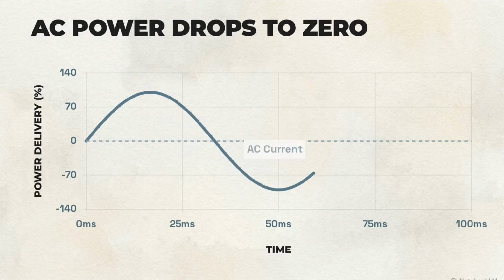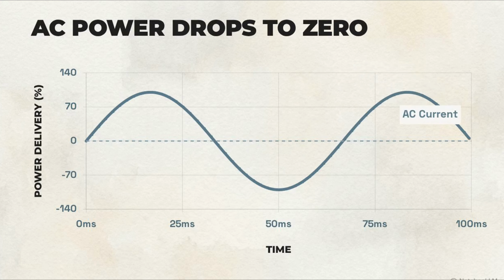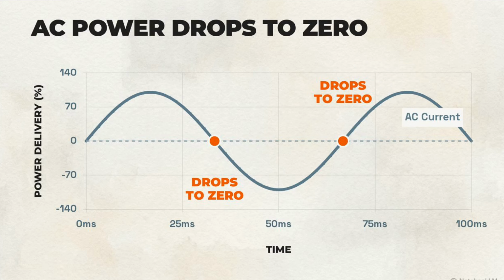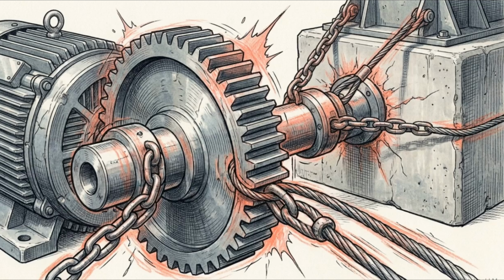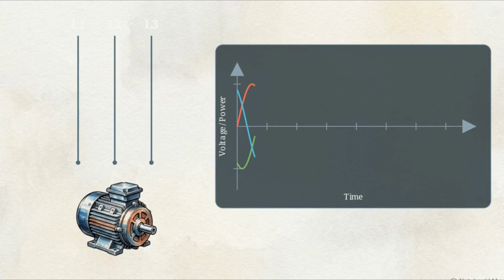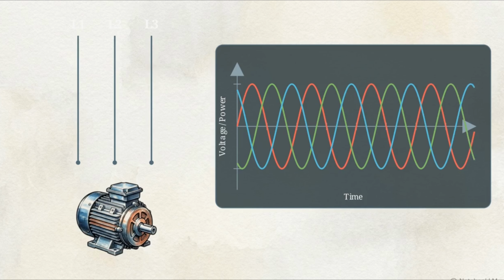However, a single line of alternating current oscillates back and forth, meaning the power delivery actually drops to zero at the crossover point of every cycle. For a massive motor under heavy load, these gaps in energy prevent the consistent torque needed to keep a heavy shaft turning. This is why heavy industry relies on three-phase power. By delivering current across three separate overlapping lines, labeled L1, L2, and L3, the system ensures that as one phase drops, the others are at peak delivery, providing a constant energy flow.